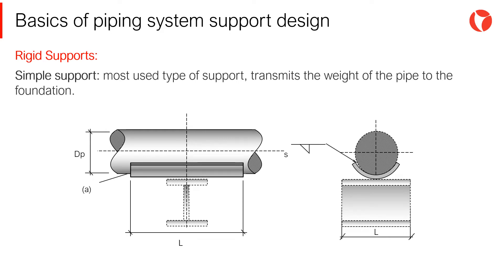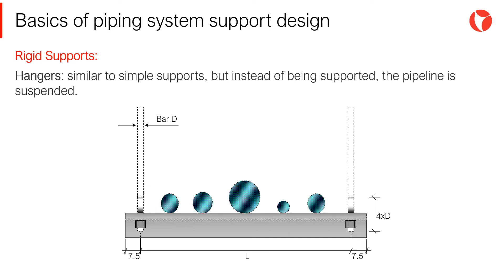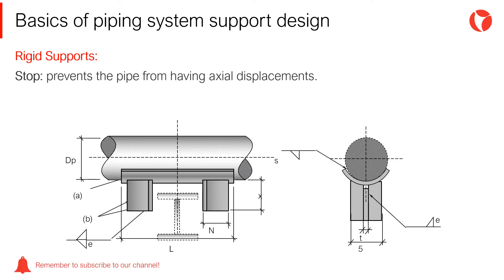Rigid supports — simple support: this is the most used type of support. Its function is to transmit the weight of the pipe and any other vertical loads to another supporting element or foundation. Hangers are similar to simple supports, but instead of being supported, the pipeline is suspended. Stops are a type of support which allow rotations but prevent the pipe from having axial displacements, and are used to limit excessive longitudinal displacements.